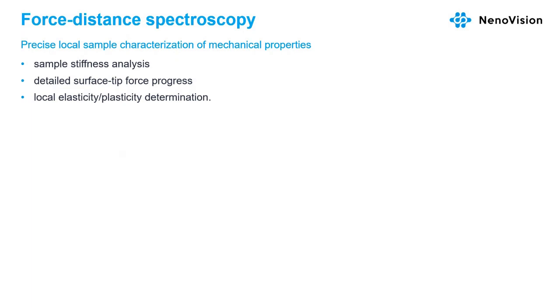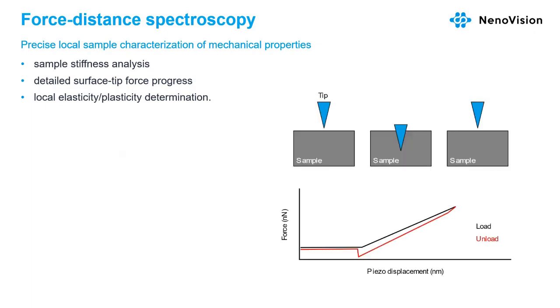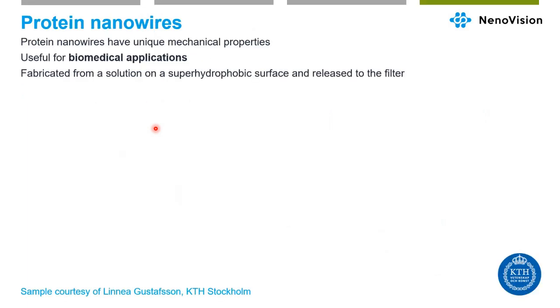Another technique for analysis of local elastic properties is force distance spectroscopy. The toughness or the sample adhesion can be measured from these curves. The area is first localized and the tip navigated to this area. Then we use the force to push into the sample while choosing the depth, and then we go away from the sample. So we see the load and unload, and we are able to know the toughness from the slope of the curve, and the adhesion. So there is different information which we can get from the spectroscopy.